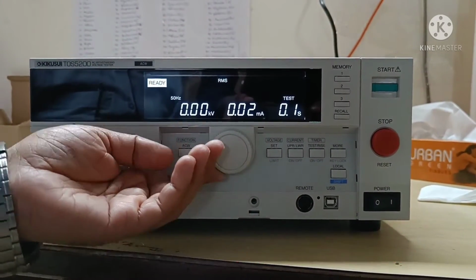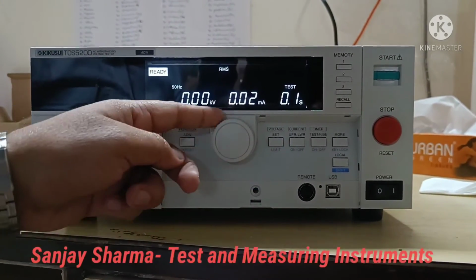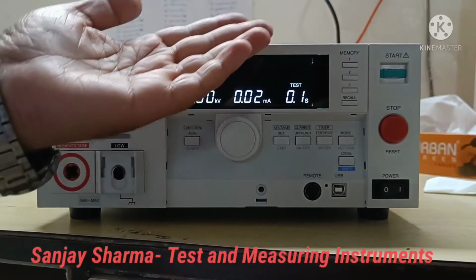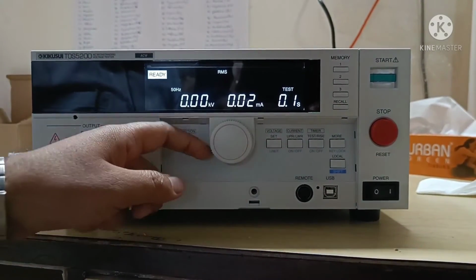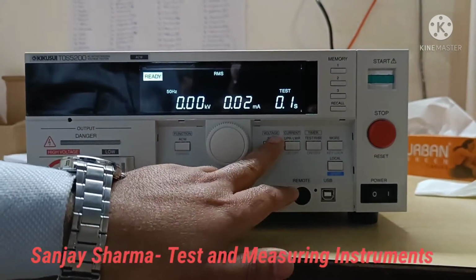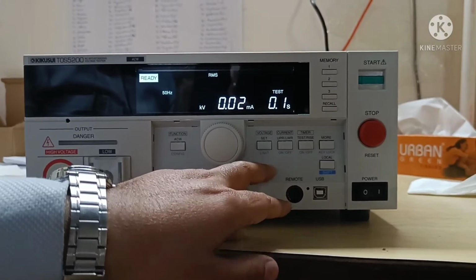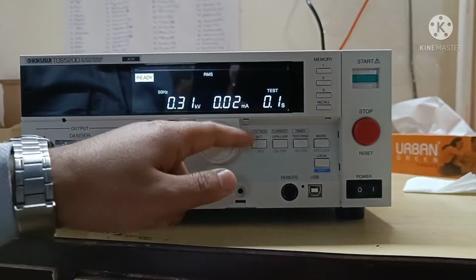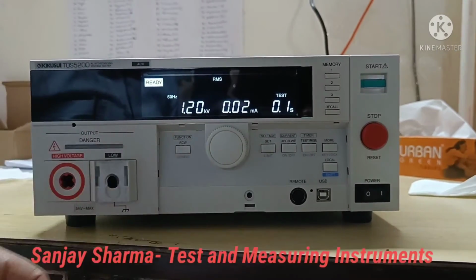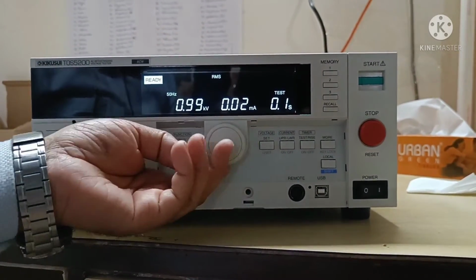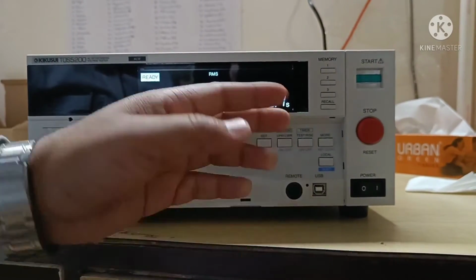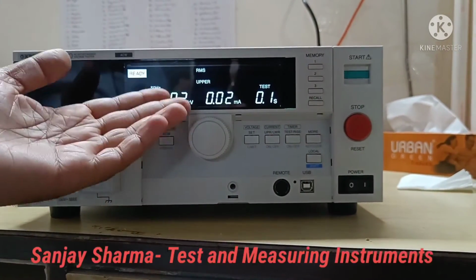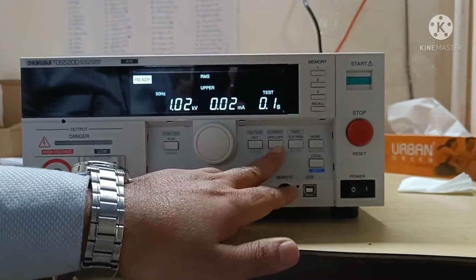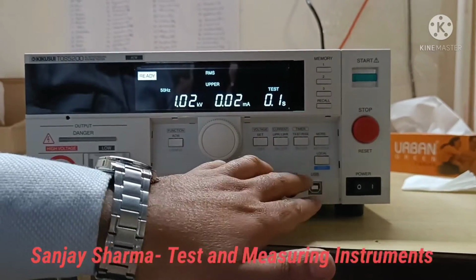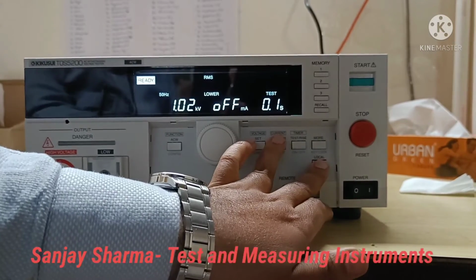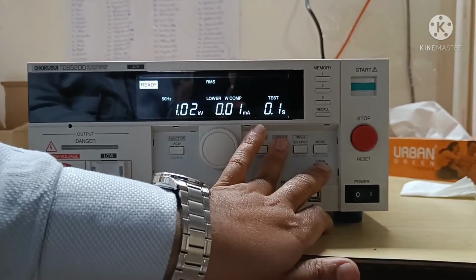This is a common encoder. Using this, we can increase the voltage levels, set the current limits, and set the testing time. Right now I'm going to set the voltage here. Once you select the voltage section, it will automatically blink. Using this encoder, you can increase or decrease the voltage as per your testing requirement. This is the upper limit and the lower limit for the current function. Depending on your requirement, you can set the upper limit as well as the lower limit. To switch between lower and upper limit, you need to use the shift key, so we can make the lower or the upper active.